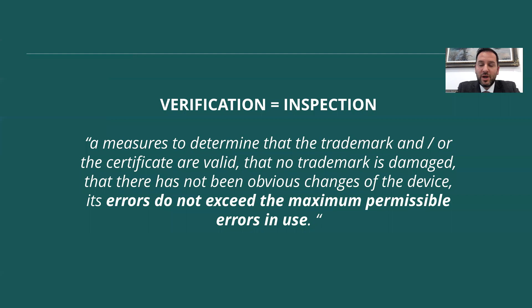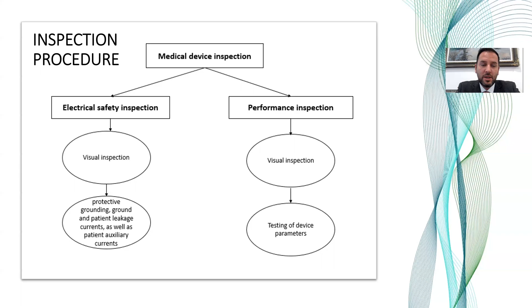Definitely, we can say that the goal of inspection or verification is to determine the output error, because by using those etalons we are able to determine the error between the measurement on that medical device and the accurate measurement from that etalon. For somebody who is not in this field, it's very important to mention that inspection, which is defined per the ISO 17020 standard, and verification are the same terms.